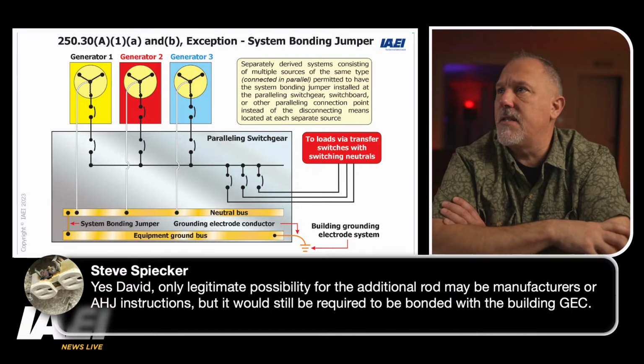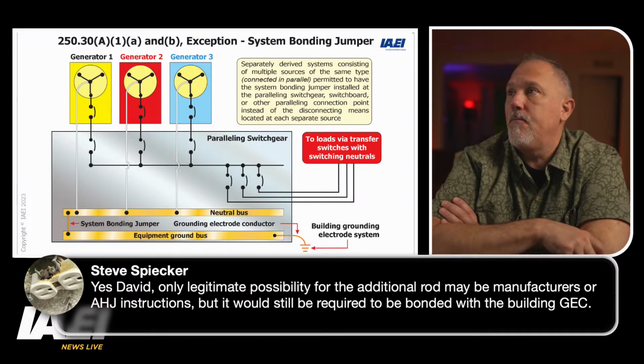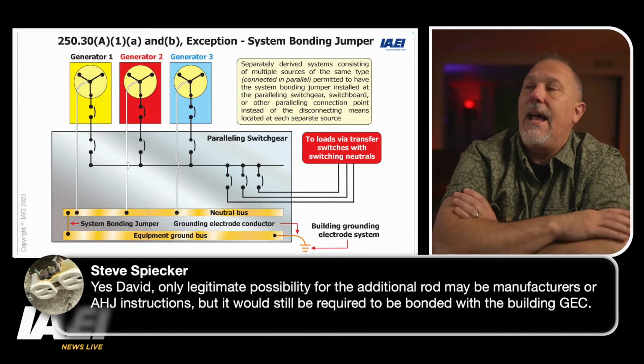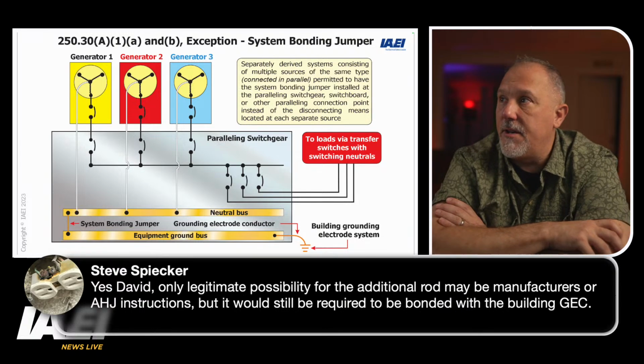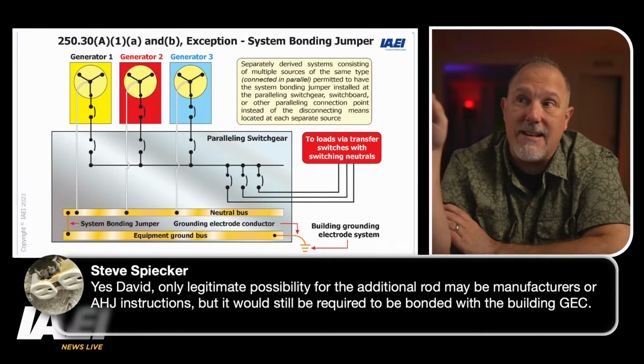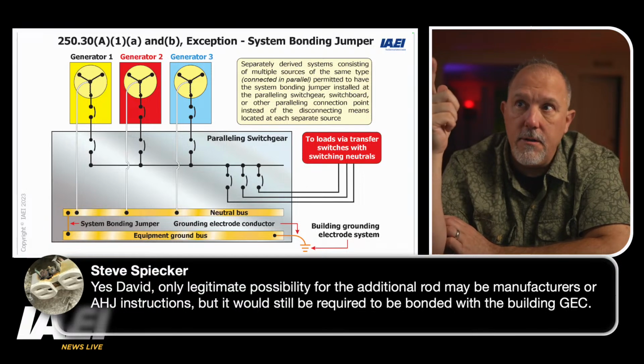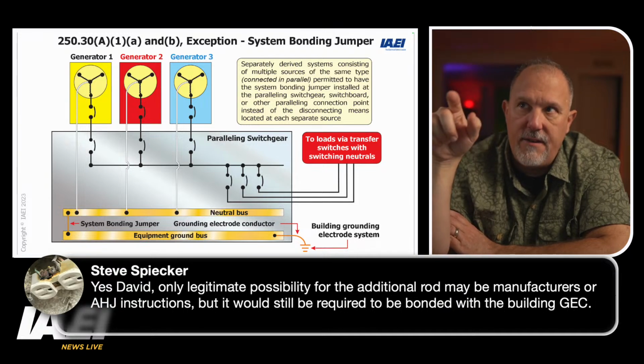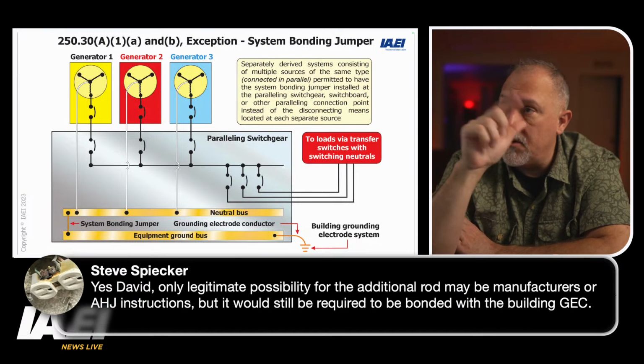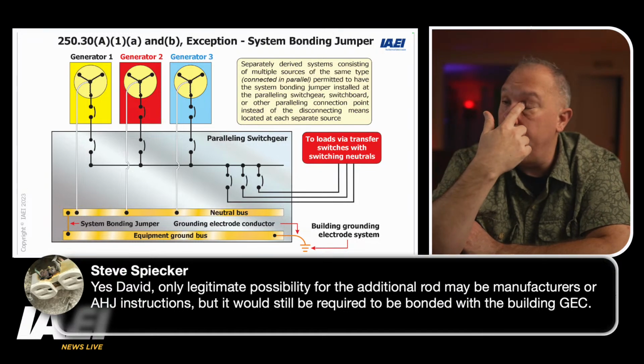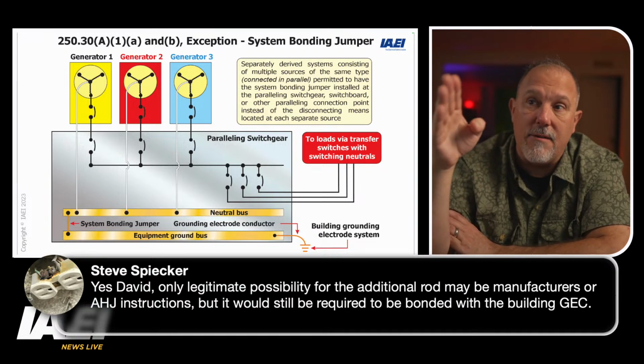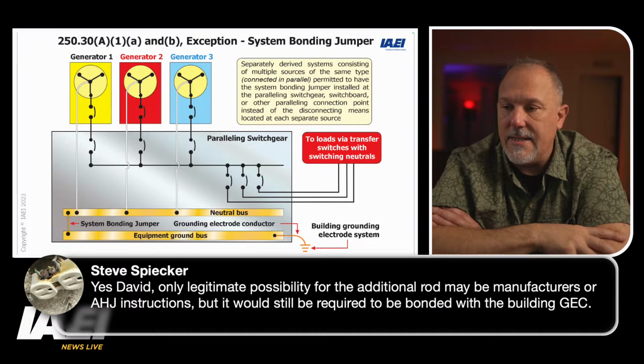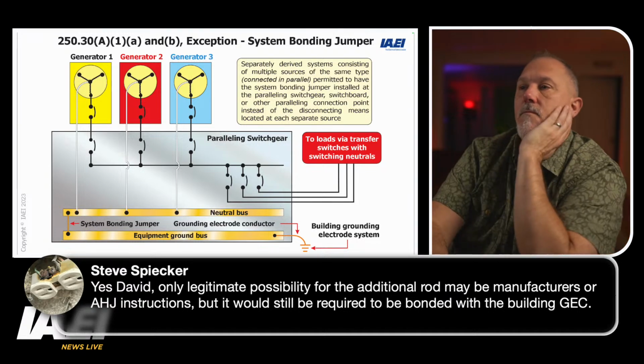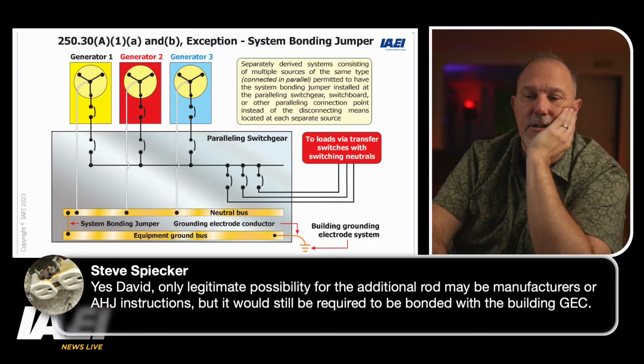All right, separately derived systems consisting of multiple sources of the same type, permitted to have the system bonding jumper installed at the paralleling switchgear, switchboard, or other paralleling connection. Now, this is the paralleling. Remember, we talked about this earlier. And you have your 3 generators, and we're showing one line for all 3 phases, but you would have A, B, and C coming off of each of those generators. So we're showing one line. It's a one-line diagram and a breaker, but then we're breaking out the grounded conductor and showing how all of that ties together. So that's a good image there.